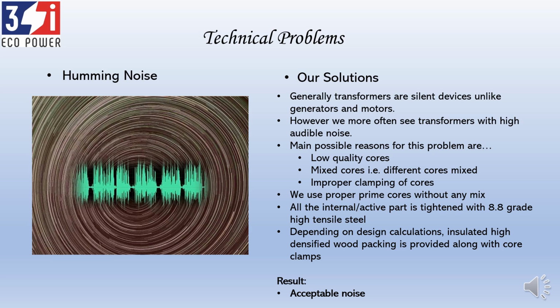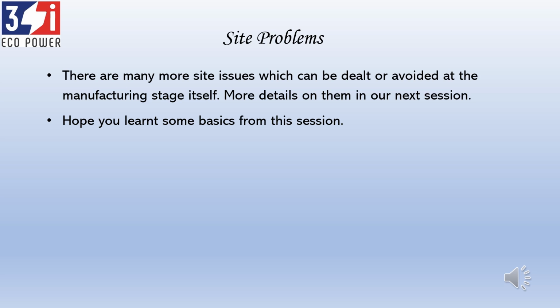But if you are using normal 4.6 grade steel or anything lesser, they may come off because of the vibrations they face. These are things we take care of, and we make transformers as per the accepted noise levels. We also take due care that the life of the transformers will not be damaged by any looseness in the fasteners over a period of time. With this, we come to the end of this session, and we will come with many other site issues which can be contained or easily attended to at site itself. We'll meet in our next session on these further things.